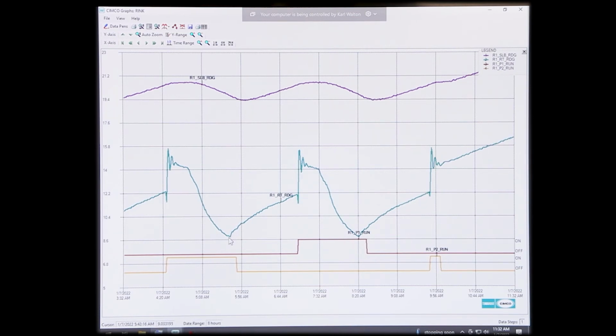So you can see at the lowest point, right before it shut off, if we look there and now look to the bottom, we can see that the return temperature got down to 8.8 degrees. Okay? Probably with 3 machines on, I would guess, to get that cold. And exactly what time it did that. And then you can see again when it restarted, hover right there, and it tells you at 15.48 degrees it restarted the pump and started restarting the compressors.